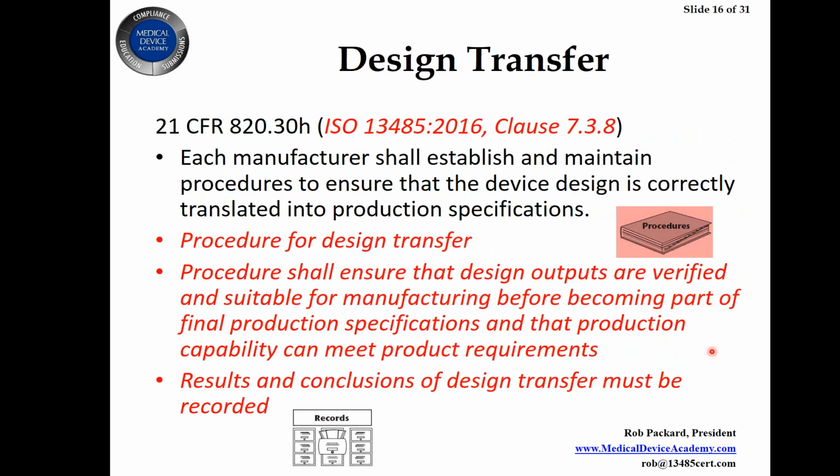It was required by the FDA, but people sort of ignored it, or they embedded it in part of their design control procedure and didn't have a really good way of documenting that they have design transfer under control, such as a checklist for design transfer. So that's one of the tools you might have. You don't have to have a separate procedure. You can embed it in your design control procedure, but you should have something very clearly identified as a design transfer document to make it clear how you're verifying the product has been transferred adequately to production.